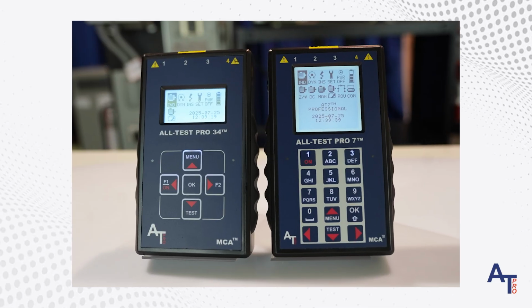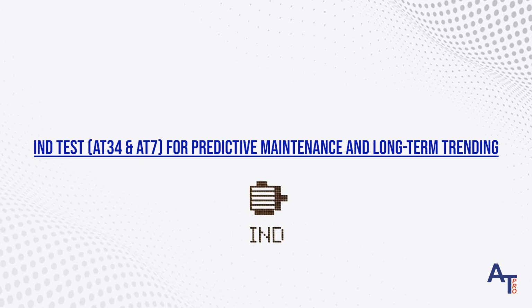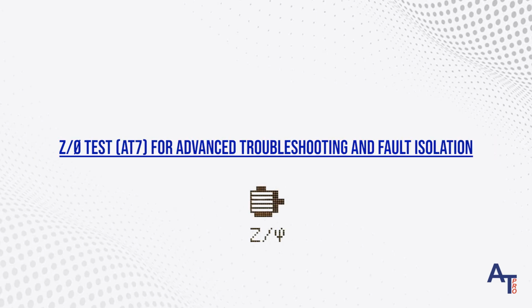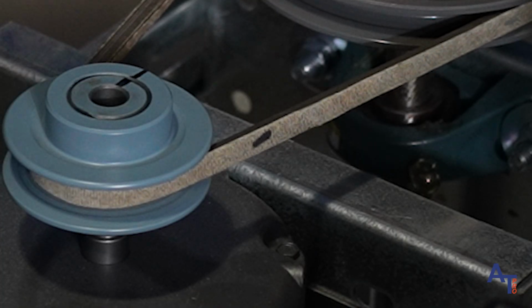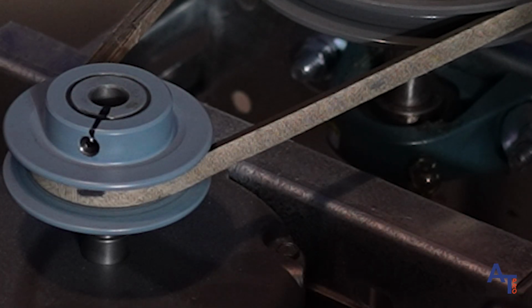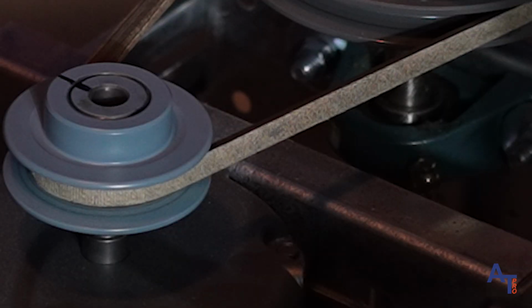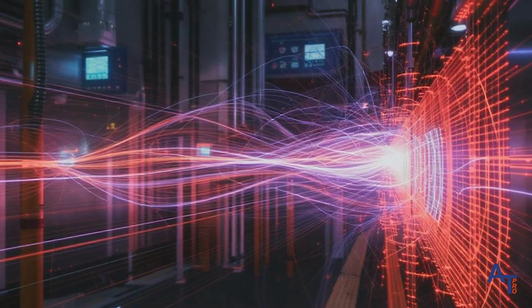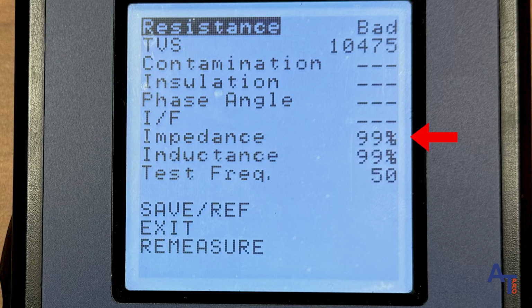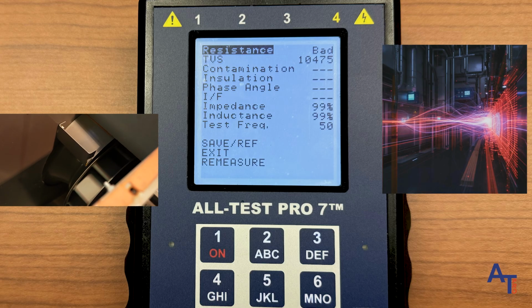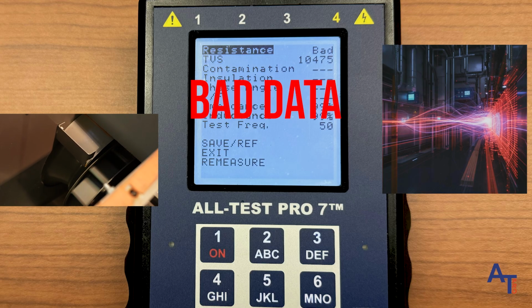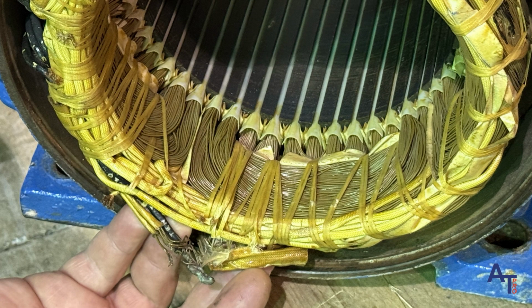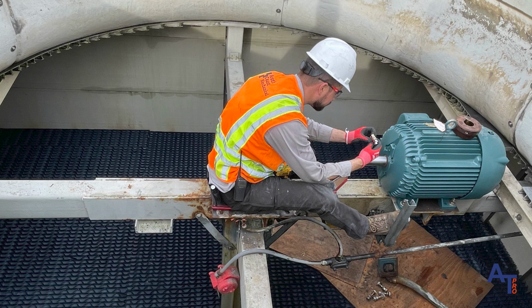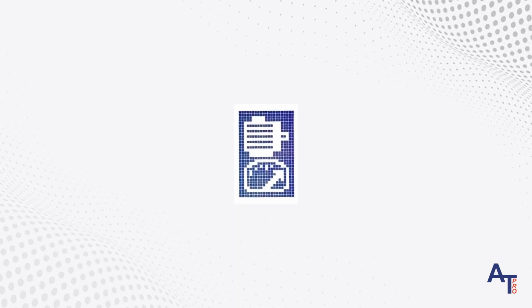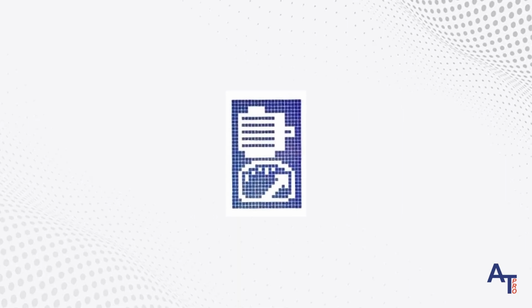The real-time test complements ATP's more advanced patented MCA methods of motor evaluation like the Ind and Z Phi tests. The Ind and Z Phi tests require a stationary shaft and an environment free from electromagnetic interference, EMI. When unstable readings occur, the real-time test helps identify whether the issue is due to shaft movement, EMI, or a developing fault. Real-world testing environments aren't always ideal. The real-time test helps technicians navigate common challenges.